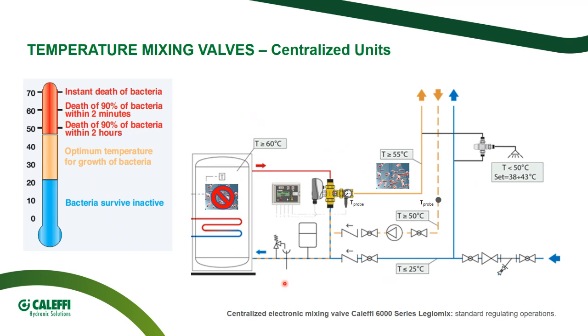In detail, what do we mean about thermal disinfection of the system? This is a schematic of normal operation of a digital mixing valve, Legiomix. We already saw that the hot water storage is safe because it is kept at a high temperature, 60-70 Celsius degrees, and so far we are safe. But before we told that for safety reason and for energy use purpose, we have to reduce the temperature.